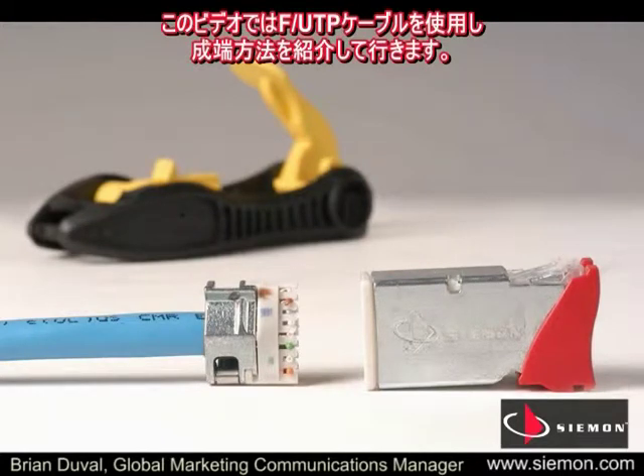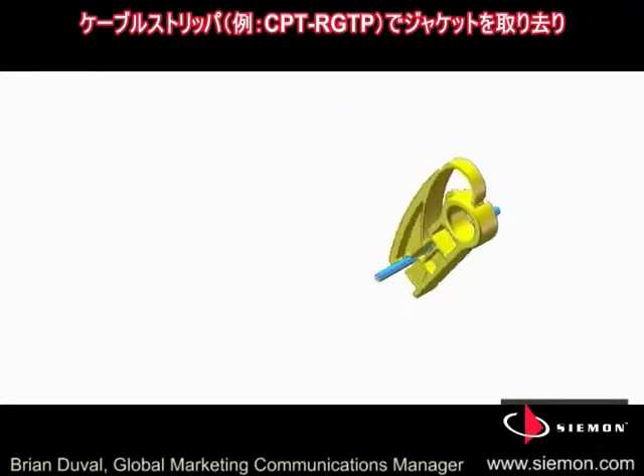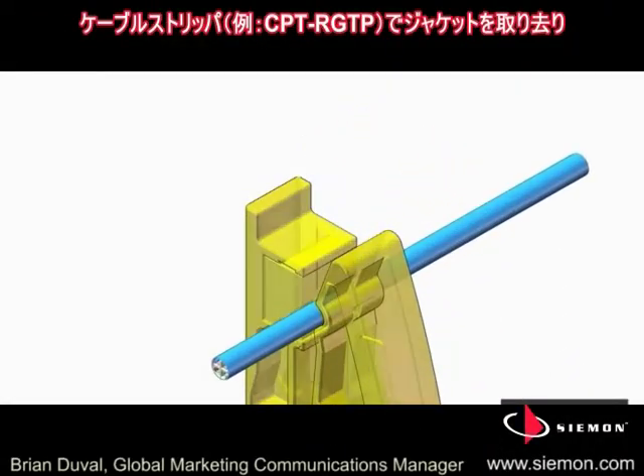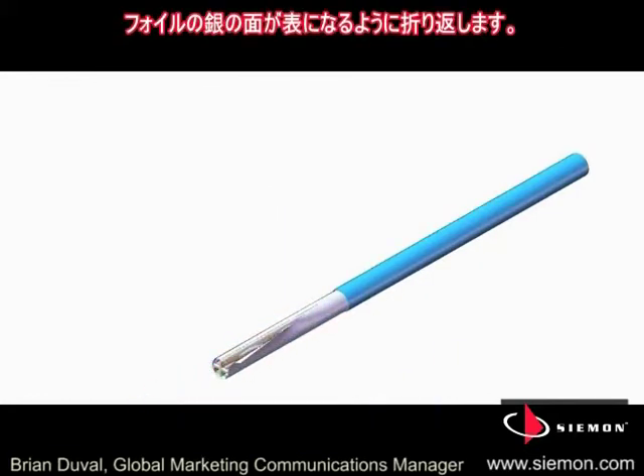The following steps show the shielded ZMAX outlet termination using FUTP cable. Using a cable preparation tool such as Siemon CPT-RGTP, score and remove the outer cable jacket and then fold back the aluminum foil.